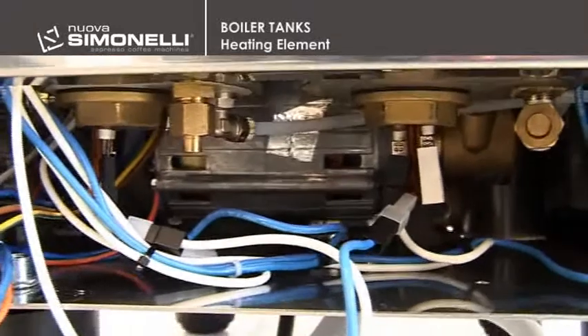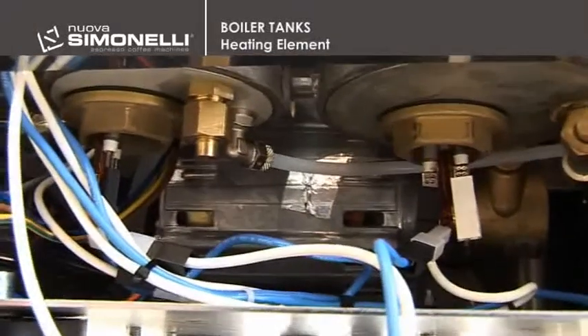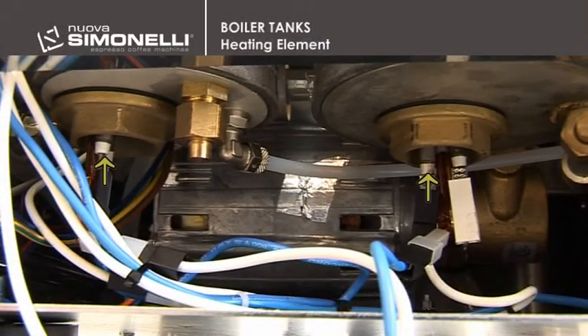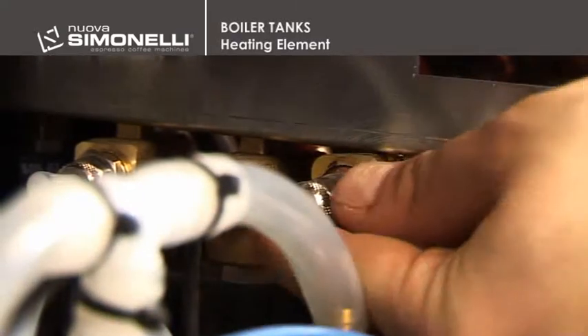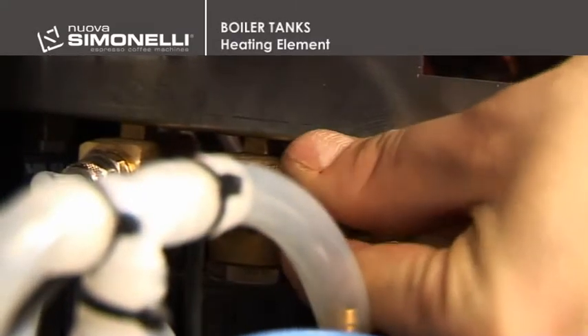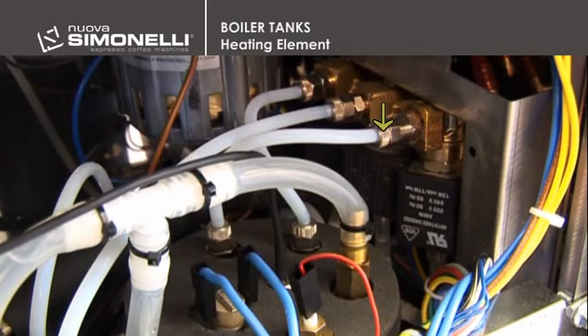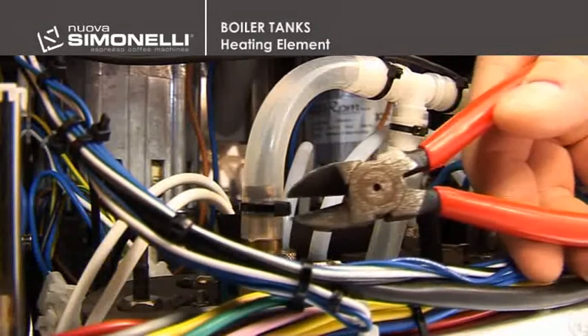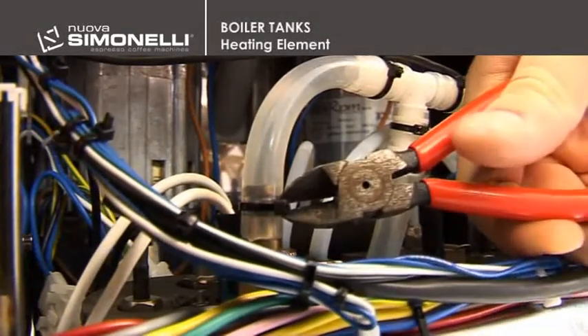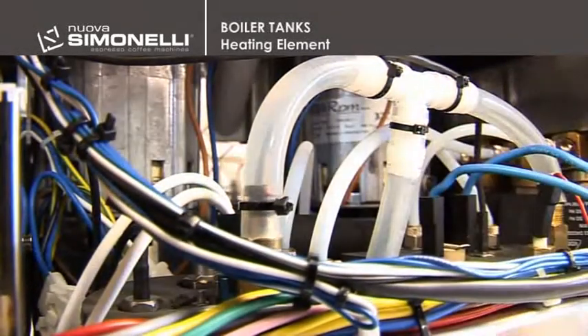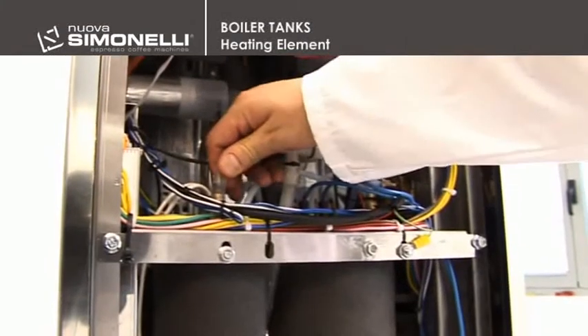Heating element. The boiler tank needs to be removed in order to replace the heating element. Once the boilers have been emptied, the engineer needs to unhook the Teflon pipe from the fittings to the steam solenoid, hot water solenoid, add water solenoid, and safety thermostat, CSA version only. Next, remove the clamp from the expansion valve and slide out the silicone pipe.